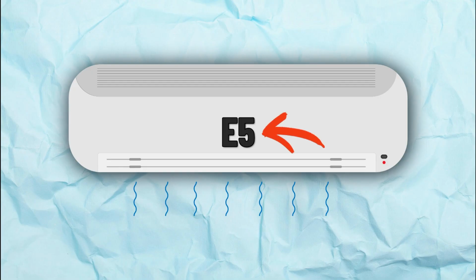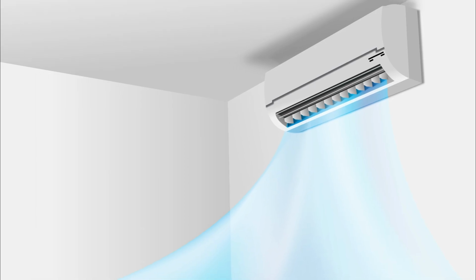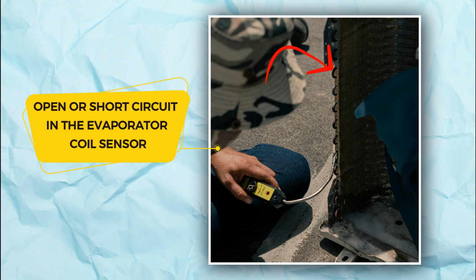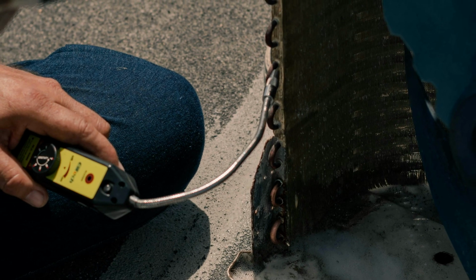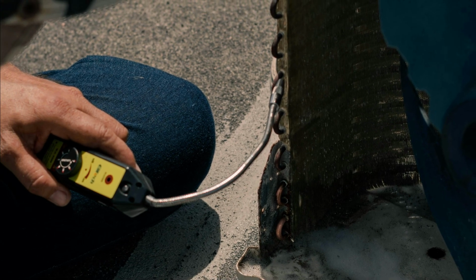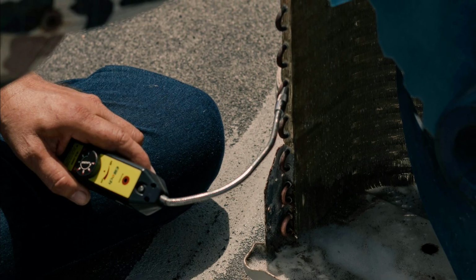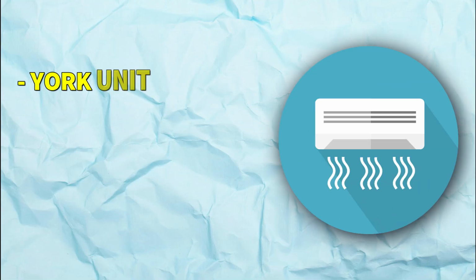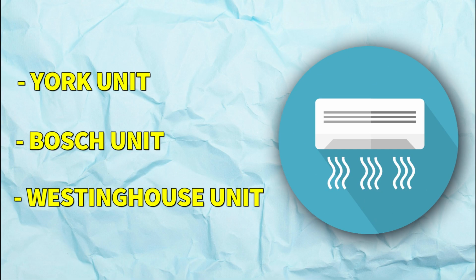Now, if the E5 error is on your indoor Carrier unit, don't assume that because it's the same brand, the same fix applies. On an indoor unit, that's usually an open or short circuit in the evaporator coil sensor. The sensor that monitors your coil's temperature is either faulty, has a wiring issue, or is sending inconsistent readings. And this also applies if you have a York, Bosch, or Westinghouse unit.